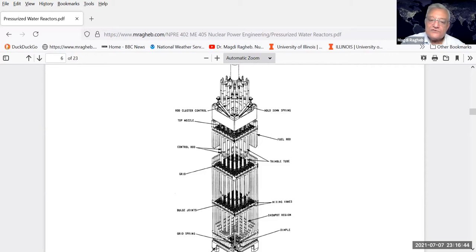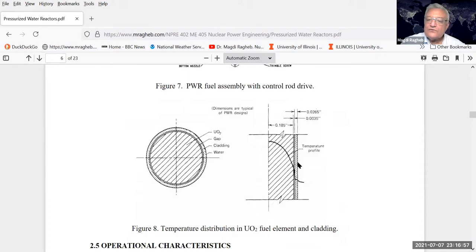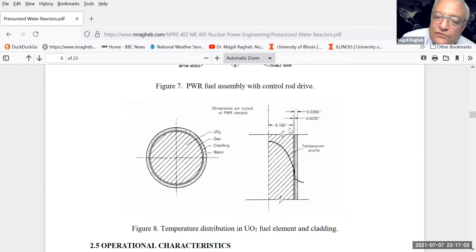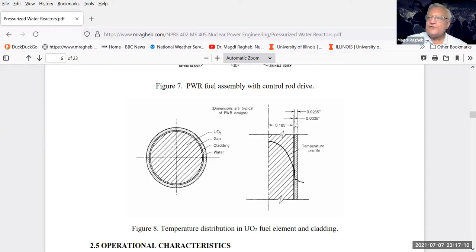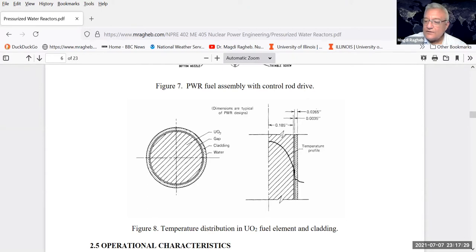Each fuel element is placed in a long rod in a 17 by 17 array for pressurized water reactors. These are the fuel rods with spacers to keep them spaced from each other. The coolant comes in from the bottom and rises over the surface of the fuel, extracting heat generated from fission. There is a temperature drop over something almost one centimeter in diameter. The helium acts as thermal bonding for heat transfer between the fuel and cladding, and also serves to detect any leak by detecting helium.